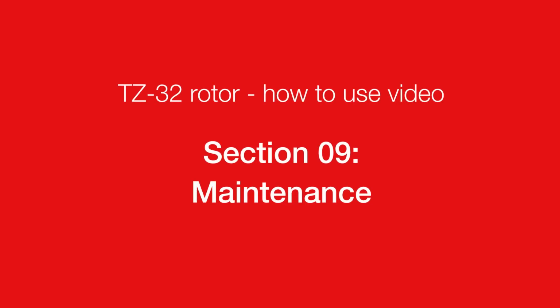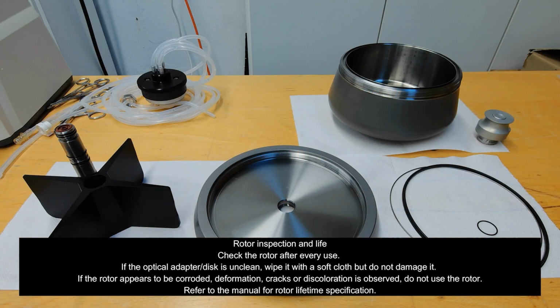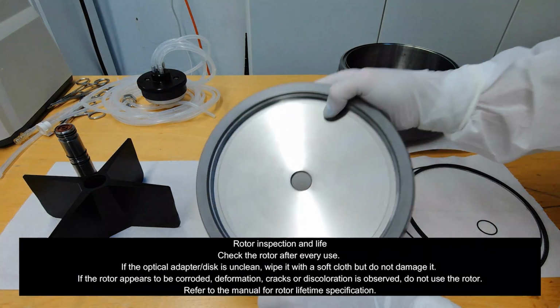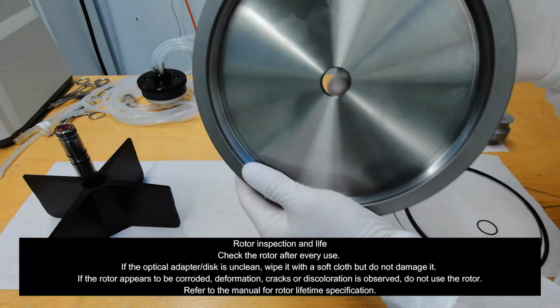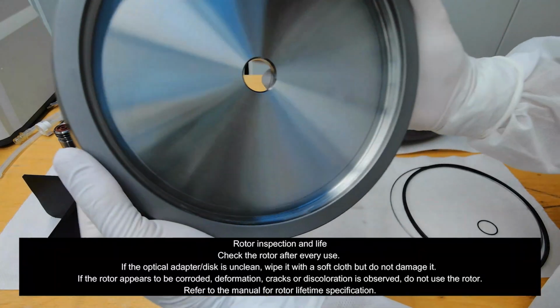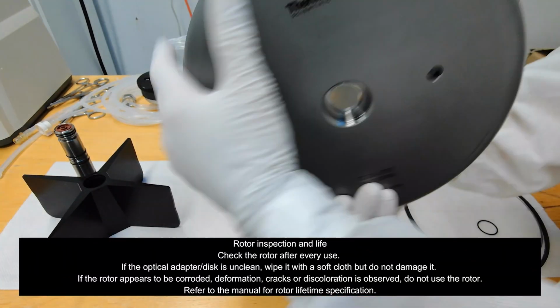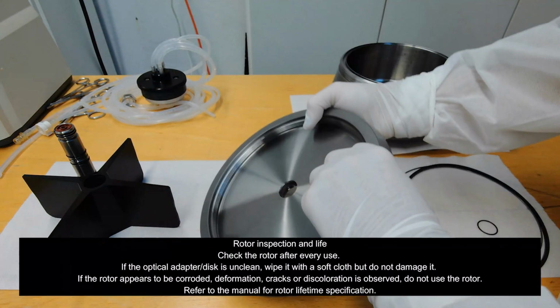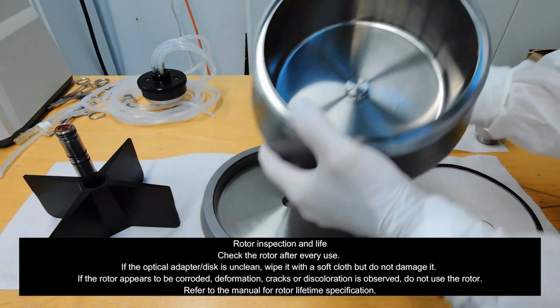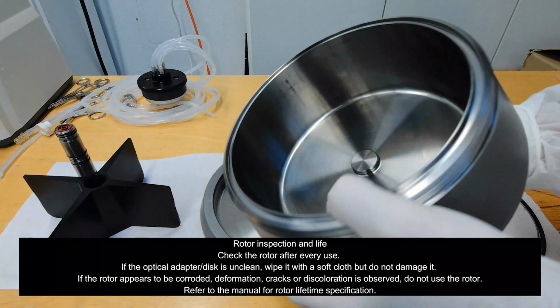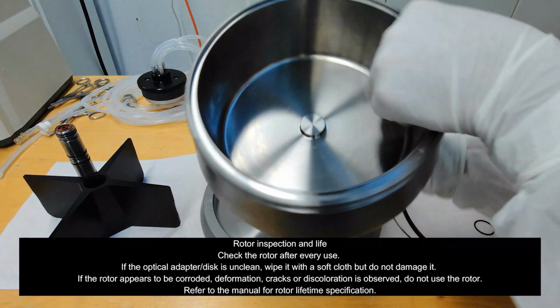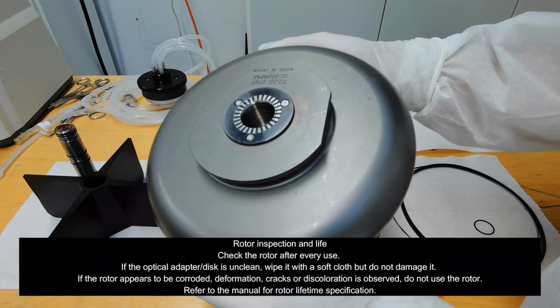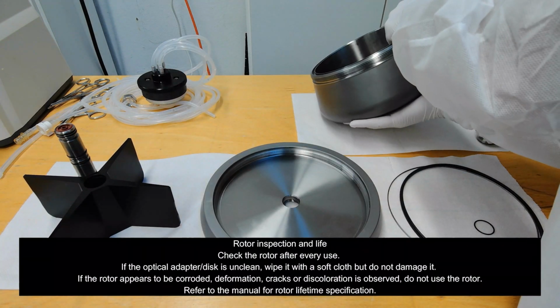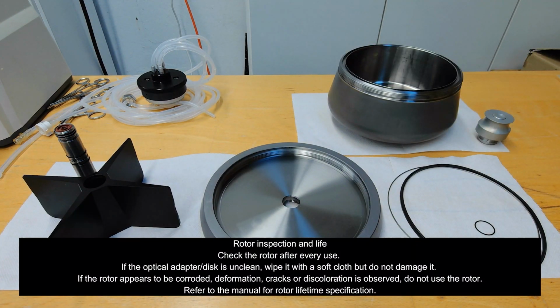How to use video. Section 9. Maintenance. Rotor inspection and life. Check the rotor after every use. If the optical adapter disc is unclean, wipe it with soft cloth, but do not damage it. If the rotor appears to be corroded, deformation, cracks, or discoloration is observed, do not use the rotor. Refer to the manual for rotor lifetime specification.